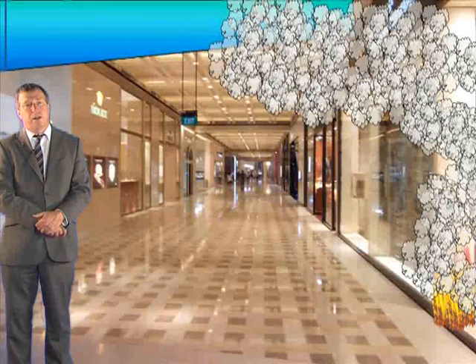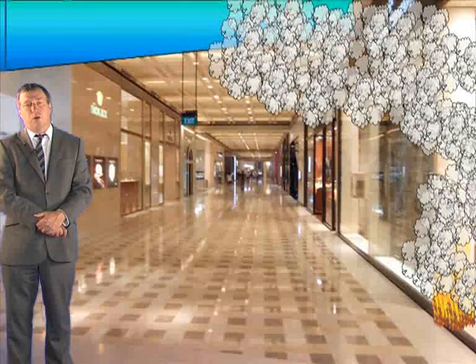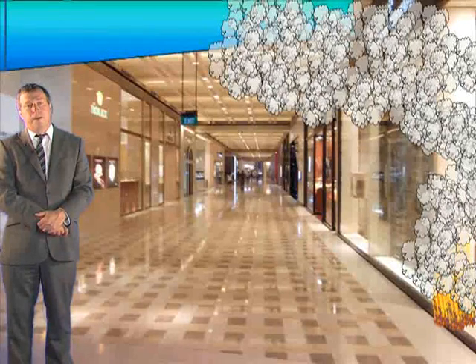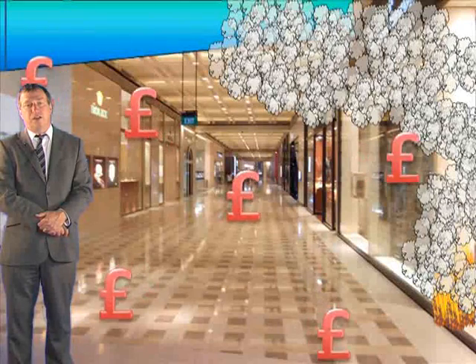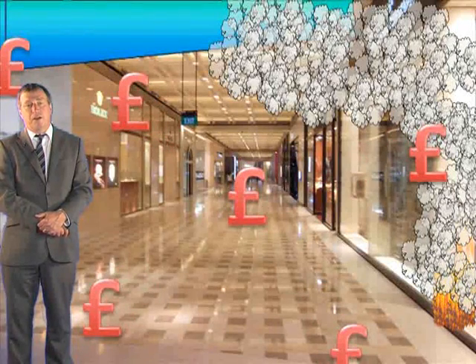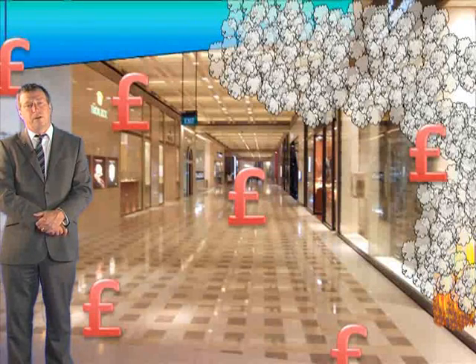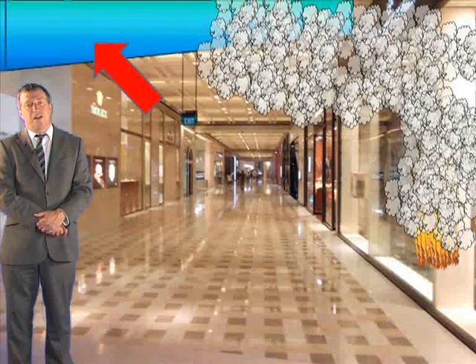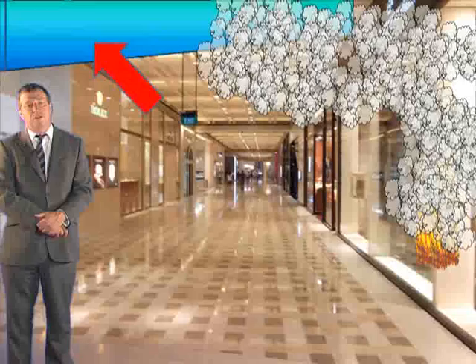that is created. This under-balcony extraction has the advantage that it limits smoke damage and facilitates a quicker and easier return to normal working conditions. Also, this form of extraction is essential where the height of rise of a potential spill plume would be so great that the prediction of the amount of smoke produced becomes excessive and unreliable. It is, however, likely to be more expensive, as much fire-rated ductwork will be required and mechanical extraction will be essential. If it's desired that the smoke is contained under the balcony, then containment screens will be required all around the area we want to restrict smoke to.